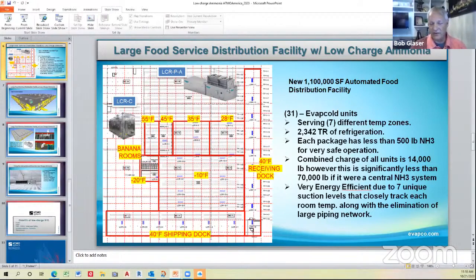Some of our other facilities, we've got quite a bit more - some of the dairies are over 34,000 pounds, and you have the flags and the testing and all sorts of alarming. We'll have the flags and alarming here too, but basically all the ammonia is on the roof. It's not near anybody, we can't run into the pipes with the forklifts, we can't hit the units. Those are always just a safety concern and a maintenance concern overall.